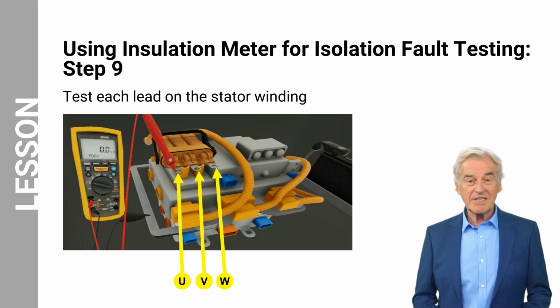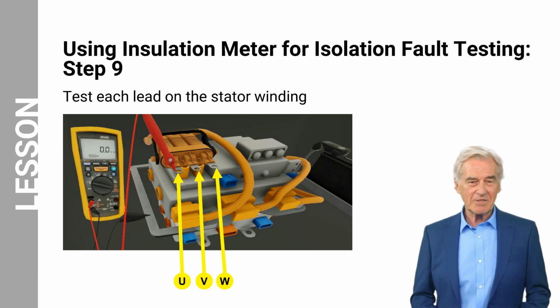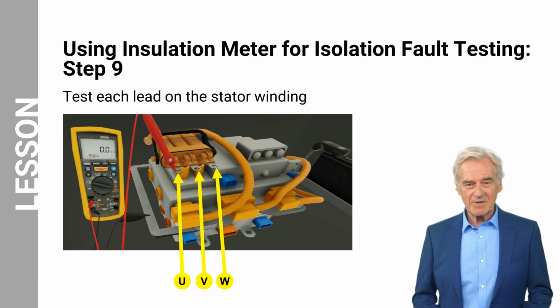Step 9. Use your insulation meter to test each lead. By performing this action, you add high voltage and low current from the positive test lead to the stator winding and attach the negative test lead to the motor housing or available chassis component. Hold either test button for 3 seconds to test the first lead. The meter readings should be infinite. As an example, in this lesson, the meter reading is displayed as 550 mega-ohms. As displayed on your screen, this process must be repeated for all connections, U, V, and W.